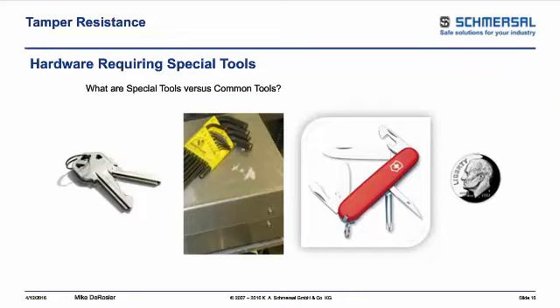that does that in order to get the intent of willful defeat or bypassing? But in cases like this picture was taken where these hex keys were right on a machine, because that was part of the tools that were given to the operator to do their job, which means the operator is capable of removing any guard on the machine because the machine did have either button head or socket head cap screws that require the hex keys or the Allen keys to be able to access. And in some cases, we find that operators are removing those as a result.